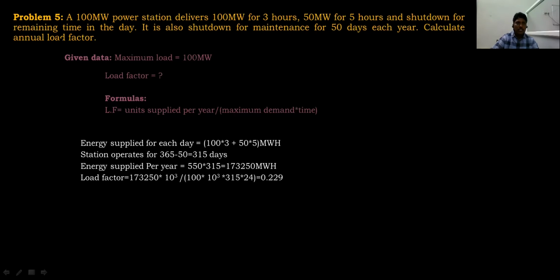And also what he asked is calculate annual load factor. Annual load factor is equal to number of units generated in a year divided by maximum demand into time. I already told you, time is 315 into 24, which we have given. Maximum demand is 100 into 10 power 3, because it is given in megawatts, as well as here 173250 megawatt hours. I already told you, if it is megawatt hours, we need to multiply by 10 power 3. Here 10 power 3 I have multiplied, and finally load factor is 0.229. Thank you.